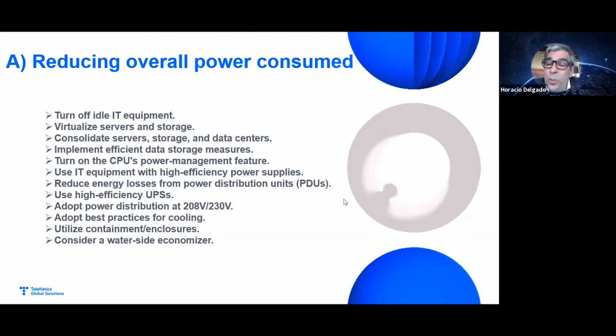We can also virtualize servers, which has been done for the past 10 years to make the hardware get the most out of servers and storage. We can also consolidate storage, implement data storage measures like SSDs, turn on CPU power management features, use high efficiency power supplies, reduce energy losses from power distribution units, use high efficiency UPSs like lithium ion UPSs that are way more efficient than legacy UPSs, and adopt a power distribution from 480 volts to 208, 200, or 230 volts.